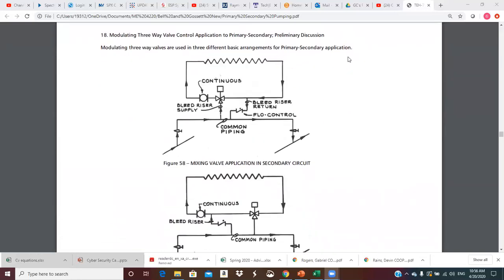Let's move on to point number 18 — modulating three-way valve control applications to primary-secondary, a preliminary discussion. Modulating three-way valves are used in three different basic arrangements for primary-secondary application. Here's a mixing valve type situation. Notice this may not be ideal because we've got that control valve pressure drop on the suction side of the pump. It's also sized for the secondary flow, which may or may not be the smallest flow. The crossover flow may be smaller, and that could be an issue.